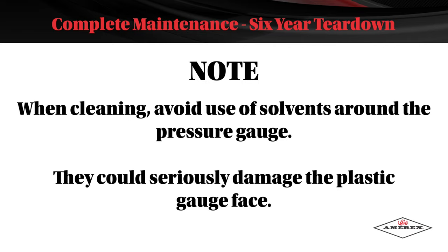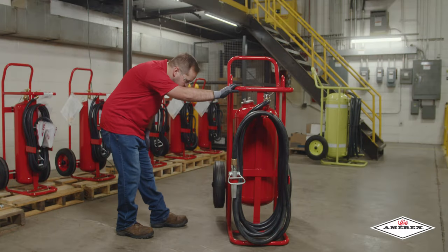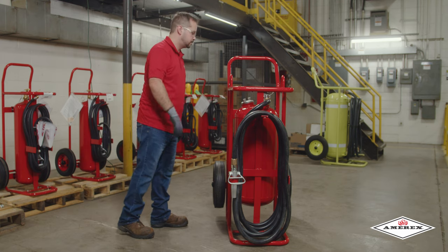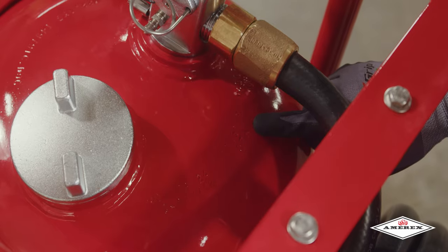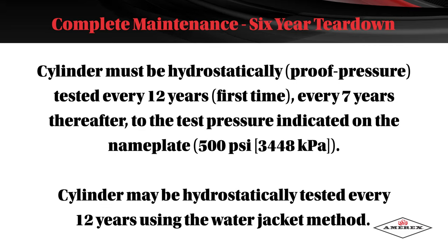Note: when cleaning, avoid the use of solvents around the pressure gauge — they could seriously damage the plastic gauge face. Inspect the extinguisher for damaged, missing, or substitute parts. Only factory replacement parts are approved for use on AMEREX fire extinguishers. Check the date of manufacture on the extinguisher dome. The cylinder must be hydrostatically tested 12 years after the original date of manufacture, and every seven years thereafter, to the test pressure indicated on the nameplate of 500 psi.